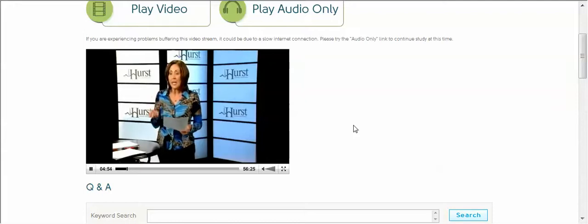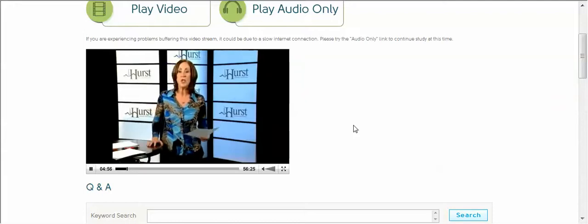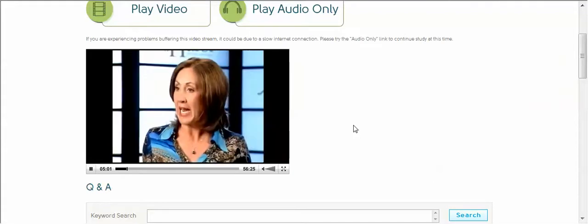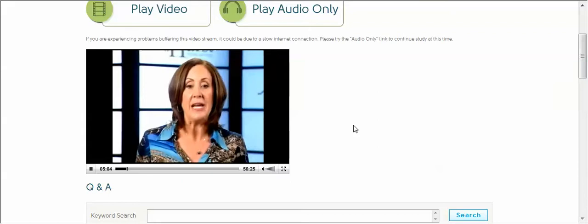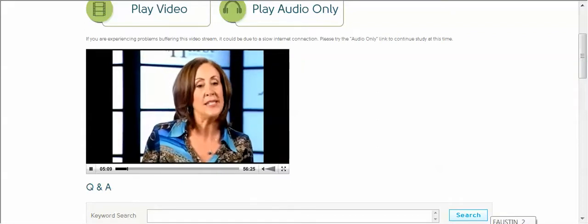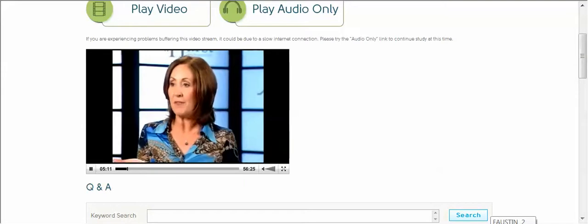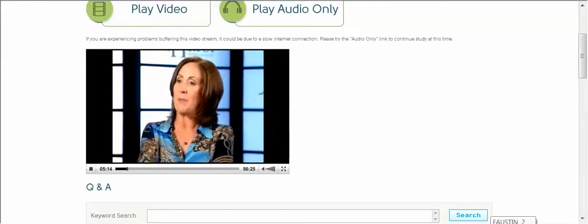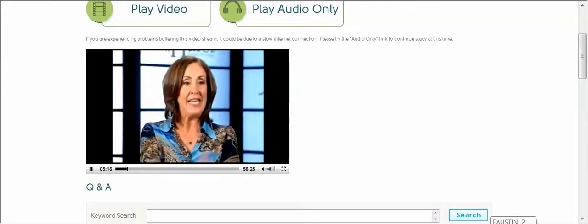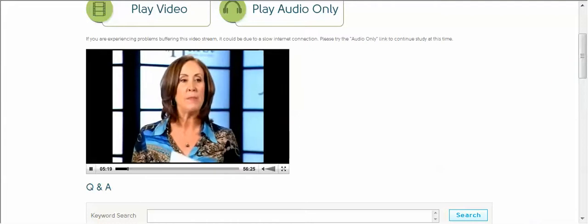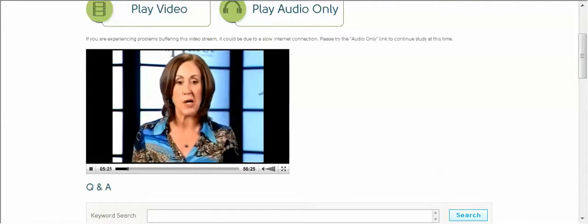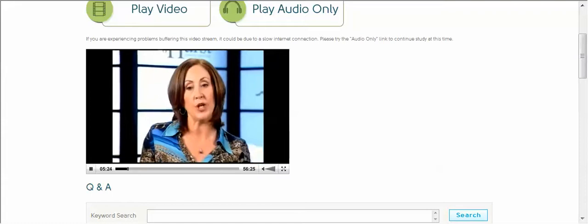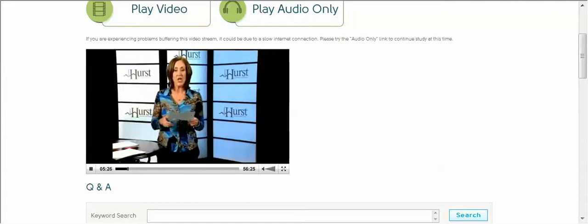Okay, a demand pacemaker is going to kick in when the client needs it to, when it's demanded to turn on. So let's pretend I have a demand pacemaker and the low rate is set at 70 for my pacemaker. As long as my own pulse is 70 or above, what's my pacemaker going to do? Nothing. It's turned off. But if for some reason my heart rate drops to 50, now what's my pacemaker going to do? Kick in, turn back on. It's demanded to kick in.